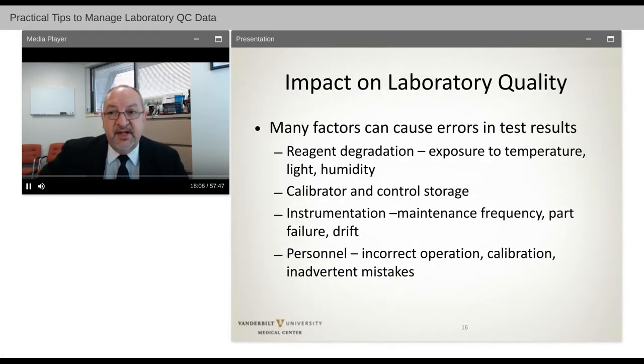Now, many factors can cause errors in test results. Reagent degradation, which is exposure to temperature, light, humidity. Calibrators and controls can go bad as they're stored, even in the refrigerator, or after we open a bottle and we repeatedly utilize the liquid in that bottle, it can be exposed to air. The analyte can shift in stability over time. So if we repeatedly run quality control out of a single vial over time, we can see degradations in performance due to evaporation or even analyte stability. So we need to think about how many times can we utilize a bottle of QC or even a calibrator after reopening it. Can those calibrators be refrozen and rethawed, which may affect performance as well?